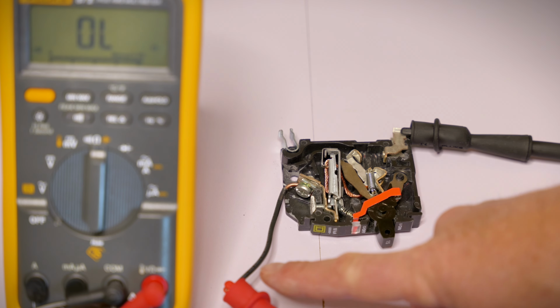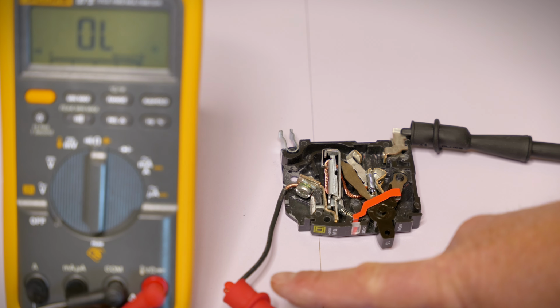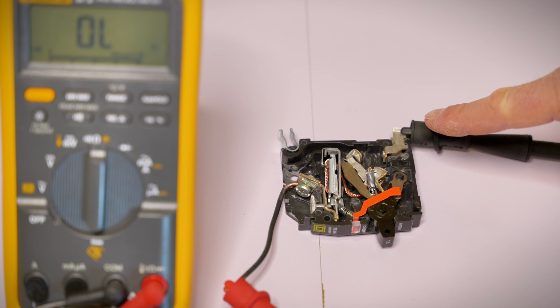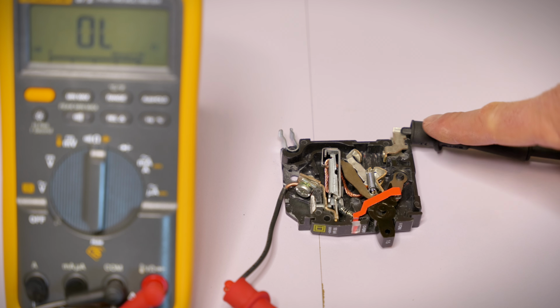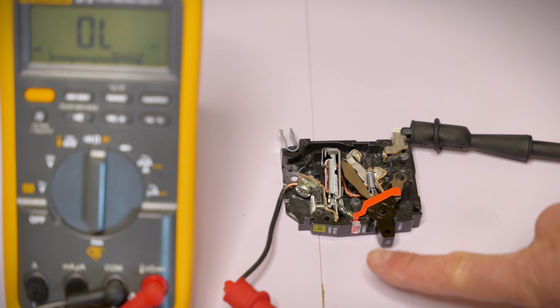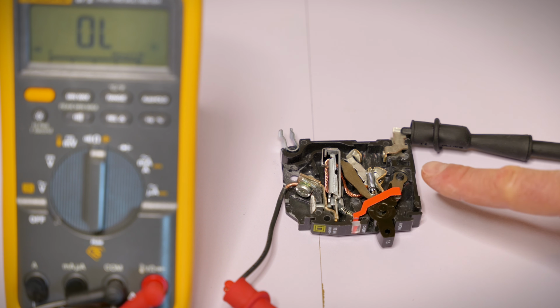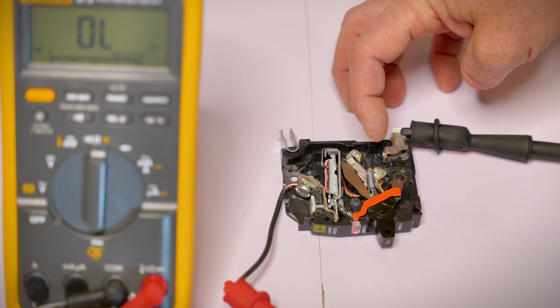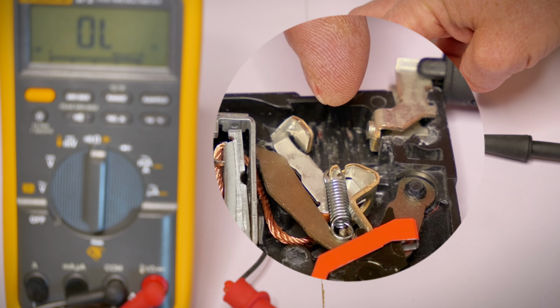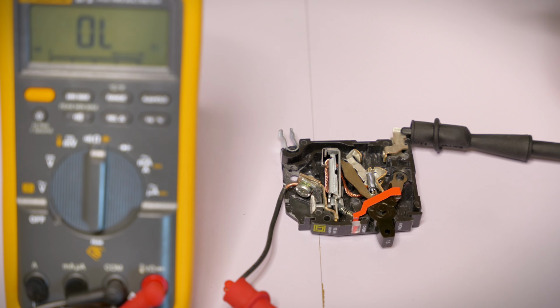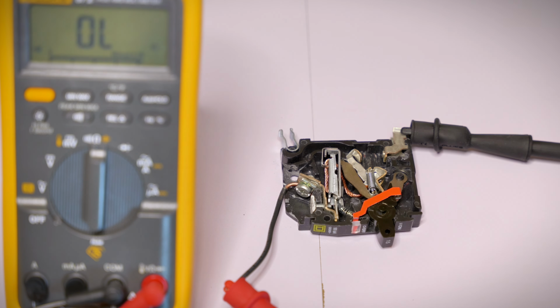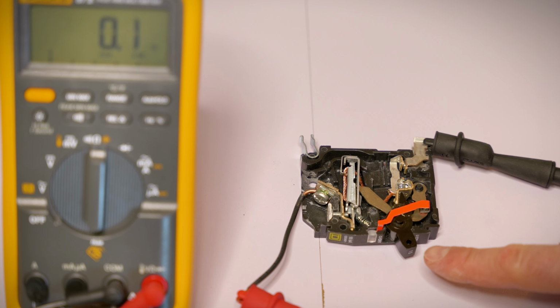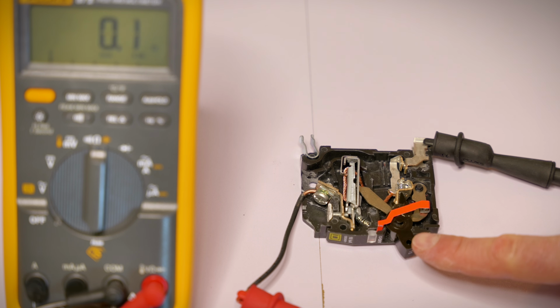Now, we've still got our meter hooked up in the ohms position. We've got our red lead on our circuit output, and of course our black lead on the bus bar contact side of it. Right now it's still in the trip position. You can see the orange in the window there, and you can also see the moving contact has separated from the terminal, thus interrupting the circuit. So right now in a normal condition, you're going to have OL, and you should no longer have continuity or the tone. And I've reset the circuit breaker. You can see now that it is in the on normal condition.